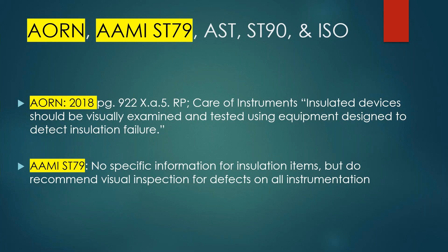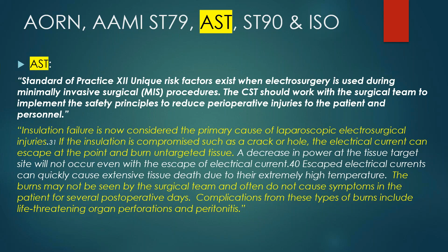AST, the scrub piece of this, the Association of Surgical Technologists, is basically saying insulation failures are now considered the primary cause of laparoscopic electrosurgical injuries. If the insulation is compromised, such as a crack or a hole, the electrical current can escape at that point and burn untargeted tissues. So they go into much detail. The burn may not be seen by the surgical team, like we talked about, but we'll go into a little more detail on the causes of symptoms that actually happen 3 to 4 days later.